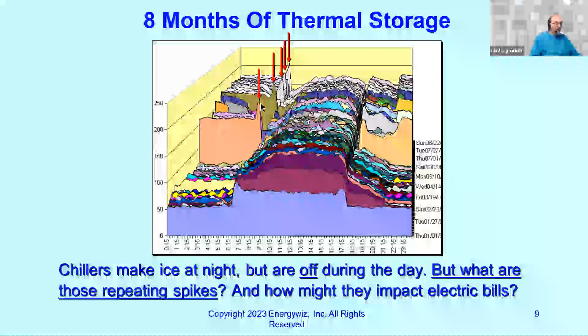But you may say there's something sticking up. What are these spikes that are sticking up here? They are driving the 24/7 peak demand charge. Remember, you have 3 different peak demand charges. This is a system for working with free cooling. Before I came to the scene, they would be running their free cooling by turning on their variable speed fans, opening up their outside air dampers when it was cooler outside than it is inside, to flush out all the heat that had been built up by the continuous base load. They would push a huge amount of air in and push it out real quick. But that raised their 24/7 peak demand up by quite a bit.